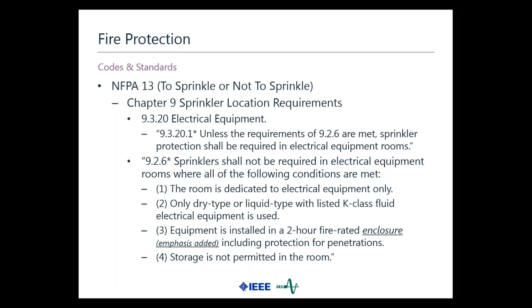That's kind of why I went over the sprinkler head ratings, to point out - hey, we always think 'oh my God, water,' but it's not going to happen that way. I've got all the conditions there, and I want to point out I emphasized it's a 2-hour fire rated enclosure. So it's not just the walls - your roof and floor have got to be rated for 2 hours as well.